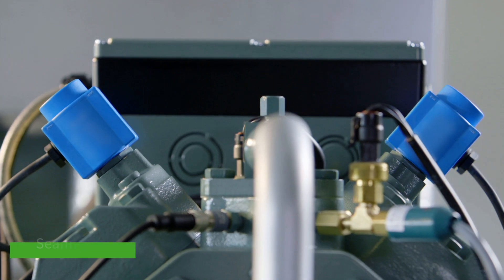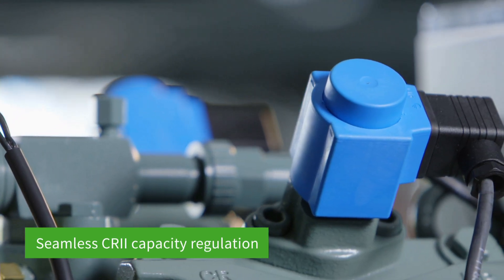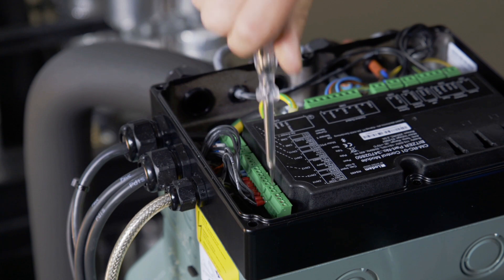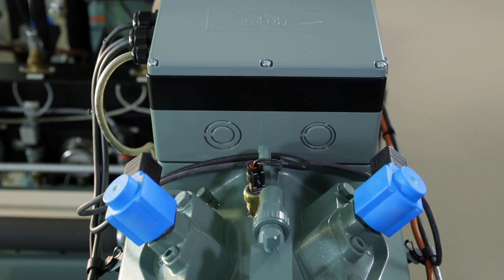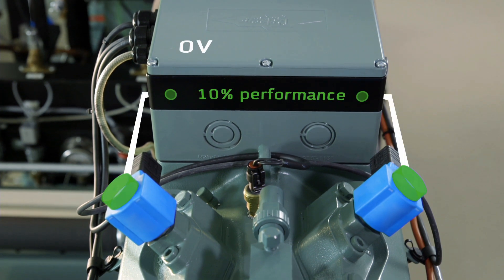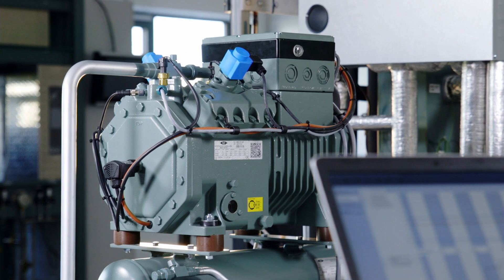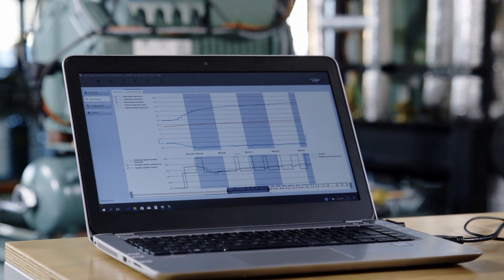Use the CR2 capacity regulation to its full potential with the IQ module's intelligent CR algorithm. As with a frequency inverter control, a 0 to 10 volt signal is sufficient. The mechanical CRII capacity regulation enables virtually seamless operation of BITZER compressors with a refrigerating capacity of between 10 and 100%. The IQ module's intelligence ensures optimum operation of the capacity regulator for extremely efficient and durable CR2 operation.